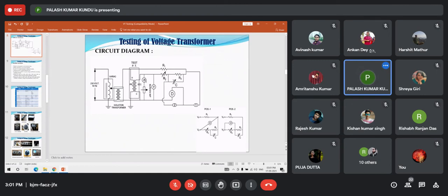How can it be done? By slight adjustment of the rheostat, so that the voltage increases and the ampere decreases, and the constant burden of 25 VA is maintained throughout the experiment following condition number 1.